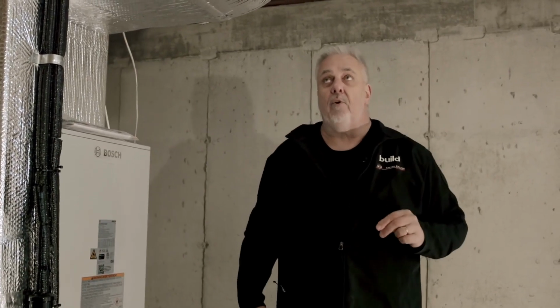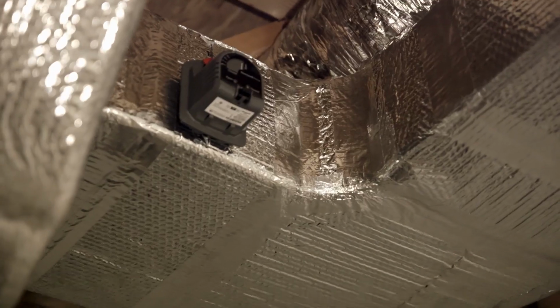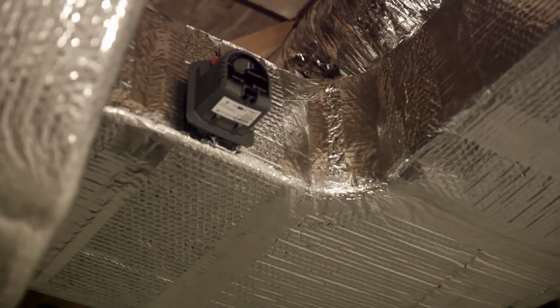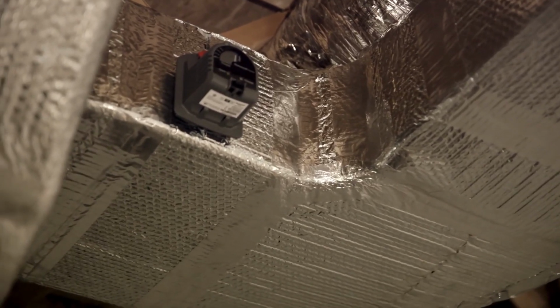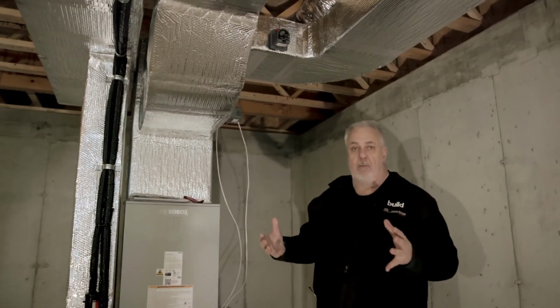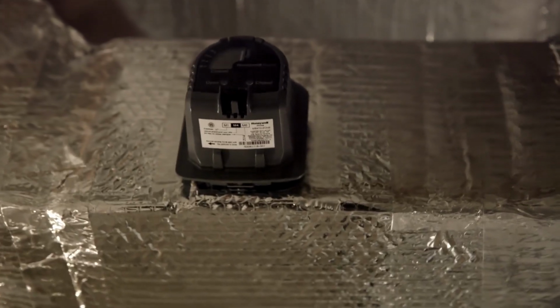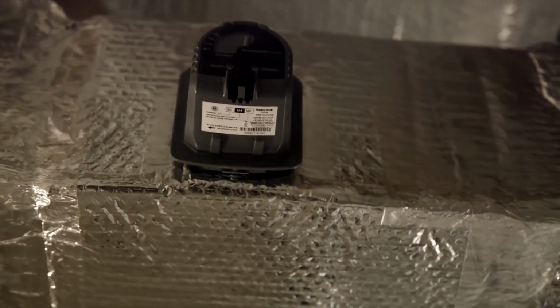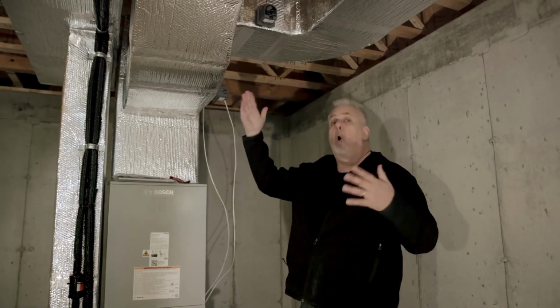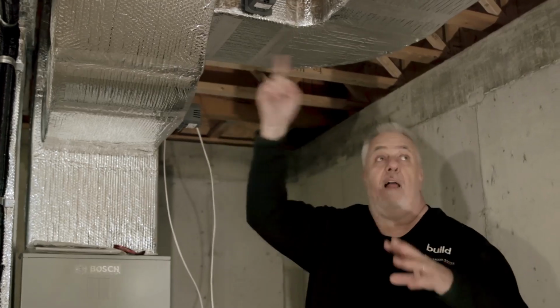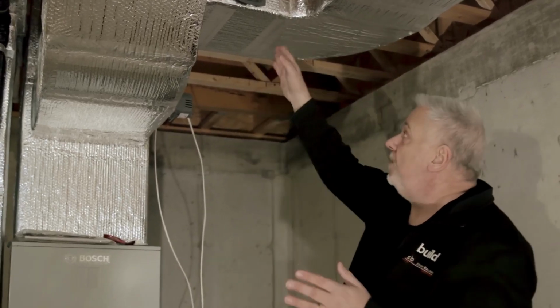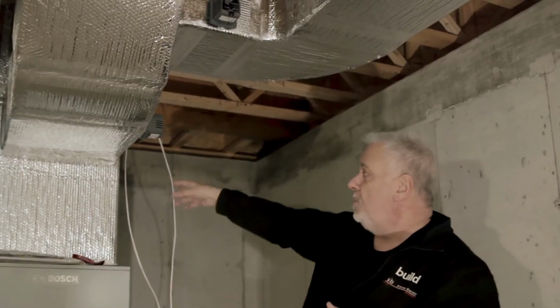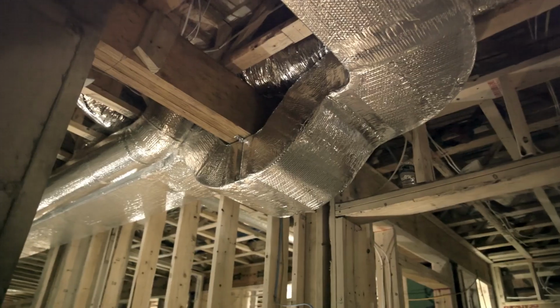Now, this unit is responsible for 2 zones - we have the basement zone and the first floor zone up above. You can see on the side of the duct here we have our zone dampers - those are basically just the brains of the operation. The damper is just a big flap inside the ductwork that is either open or closed. If it's open, it's allowing air to go down the ductwork; if it's closed, it's forcing air to go through one of the other ducts.